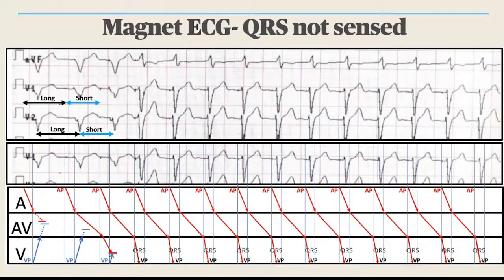Application of the magnet not only changes the pacing mode from synchronous DDD to asynchronous DOO, but also accelerates the rate of AV pacing from 70 to 85 beats per minute. This creates a long-short cycle both in the atrium and the ventricle, which is expected to be reflected in the diseased conduction system as well. This long-short sequence interrupts concealed conduction from the ventricle, but allows long AV conduction without VA block to manifest itself.